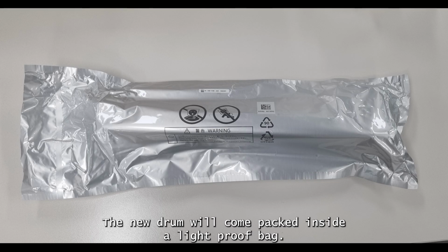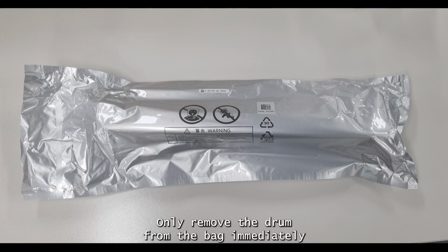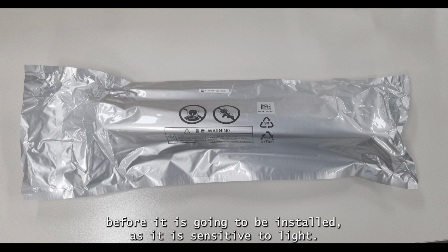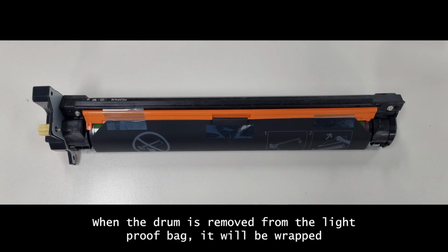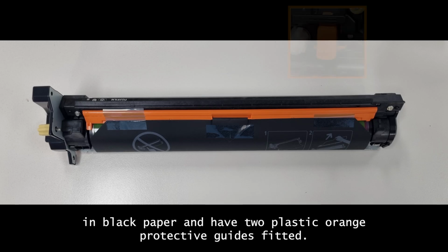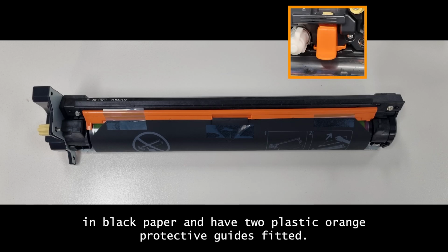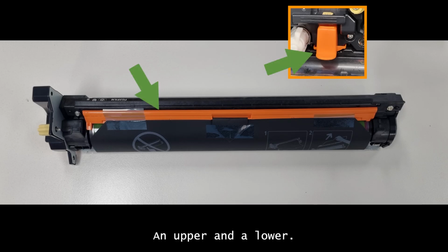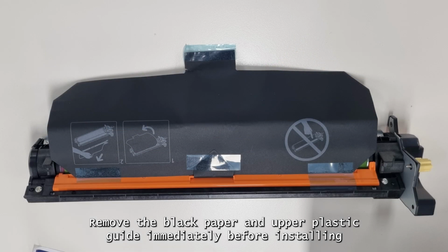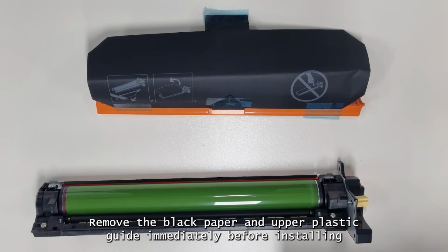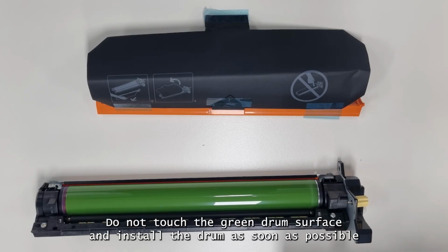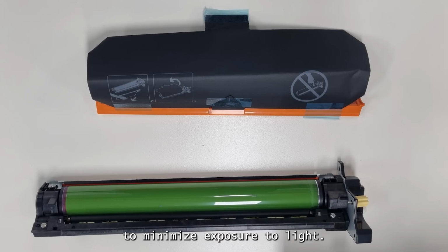The new drum will come packed inside a light-proof bag. Only remove the drum from the bag immediately before it is going to be installed, as it is sensitive to light. When the drum is removed from the light-proof bag, it will be wrapped in black paper and have 2 plastic orange protective guides fitted, an upper and a lower. Remove the black paper and upper plastic guide immediately before installing the drum. Do not touch the green drum surface and install the drum as soon as possible to minimize exposure to light.